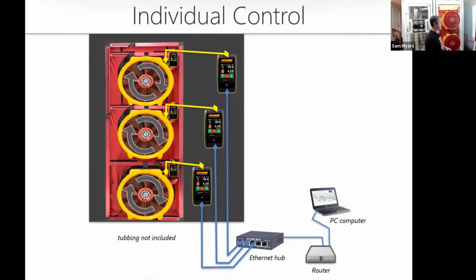The issue with that is you can get your first fan spinning, but then you have to leave the next fan covered and get it up to pressure before pulling the cover off. Otherwise, you can get the fans fighting each other, which is definitely not what you want.